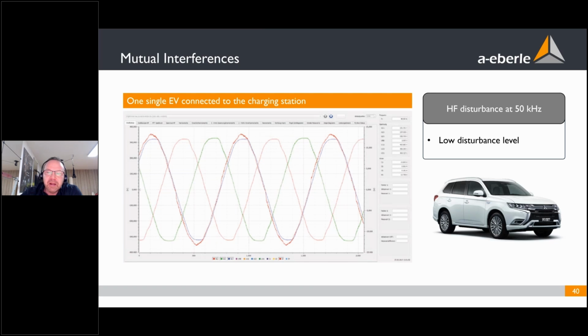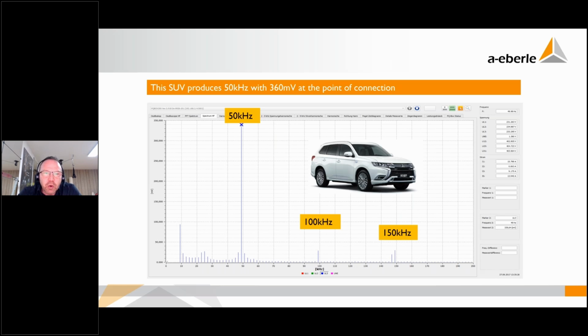Here we measure a Mitsubishi Outlander. It's a hybrid car, and the car is charging only single phase. So we charge only on phase L3. Here with voltage L1, 2, 3, only on L3 we charge the Mitsubishi. This picture I showed some slides before. Here we produce 50, 100, 150, 200 kilohertz. The 50 kilohertz interference here in the low voltage grid was about 350 millivolts.